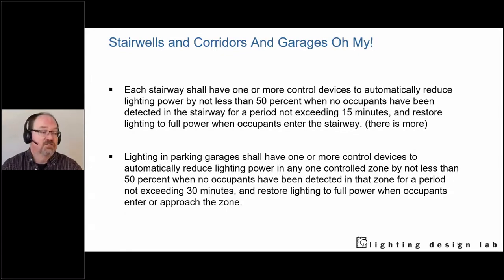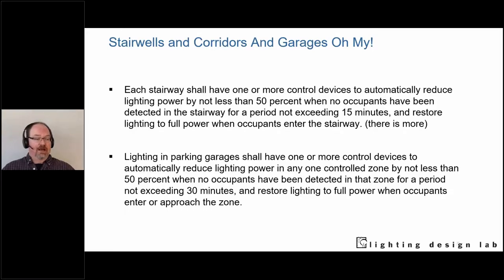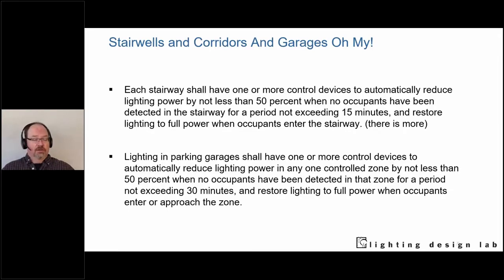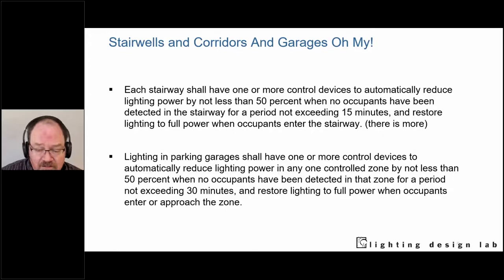Parking garages are one of the best applications for luminaire-level lighting controls. Adding wireless sensors is problematic because of all the steel and concrete mass cutting down wireless signal transmission. Running wired control cables through embedded or surface conduit is also impractical. The better approach is to put everything into each light fixture — each becomes its own individual control zone. All you need is hot, neutral, and ground. These fixtures are dimmable, you set up the programming, and life is good.